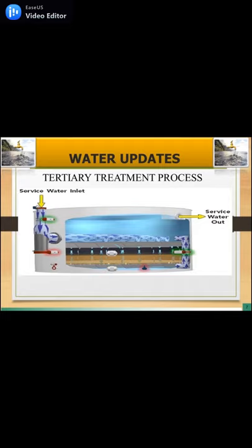Sand filtration is a process in which the treatment of the water is realized by the porous nature of a sand layer which traps particles present in water. With disc filters, the clarified effluent is polished in this step by filtering through 10 micron polyester media. The material captured on the surface of the disc filters is periodically backwashed and returned to the head of the plant for treatment.